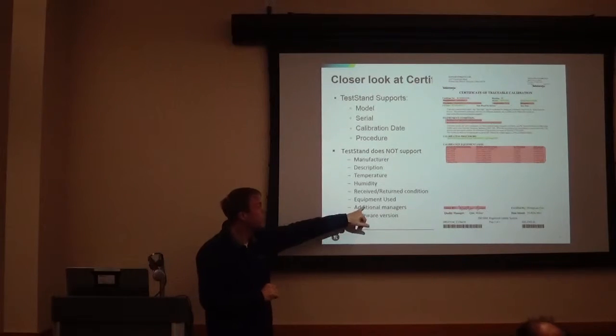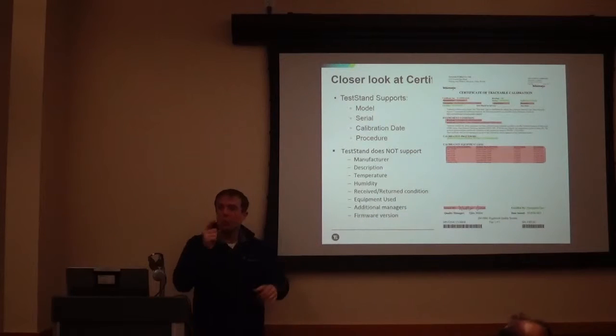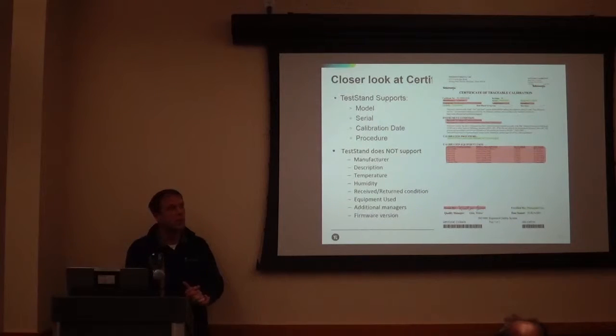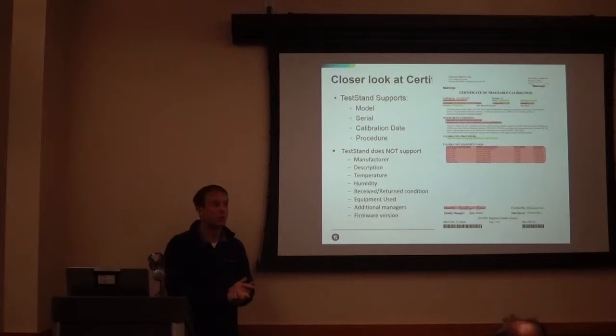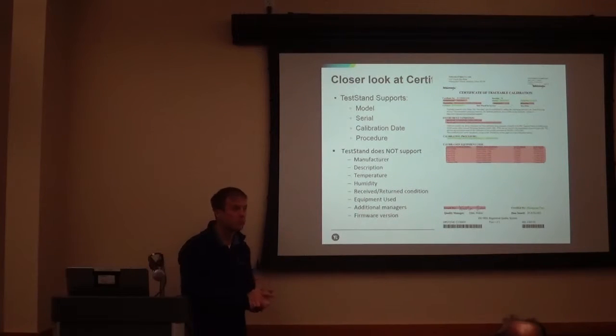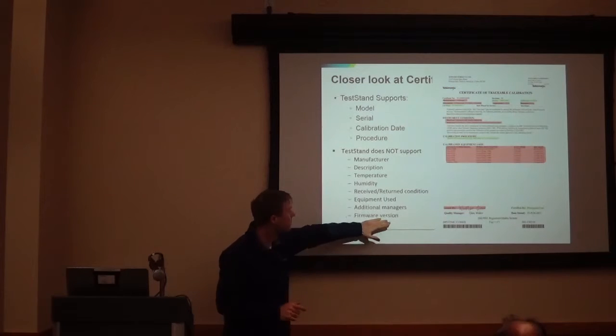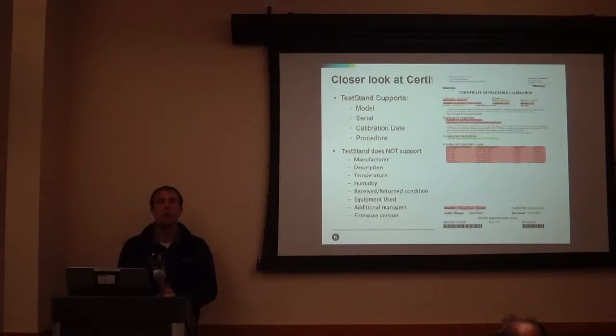And additional managers: TestStand has one user that it logs in as at the beginning, but if you're in a calibration lab, sometimes you have to have a whole chain of all the management chain and authorizers for that event. And other things like firmware versions are starting to become a lot more important in the newer standards. You should be recognizing that.